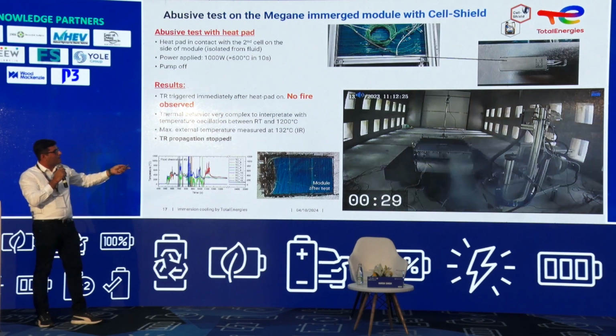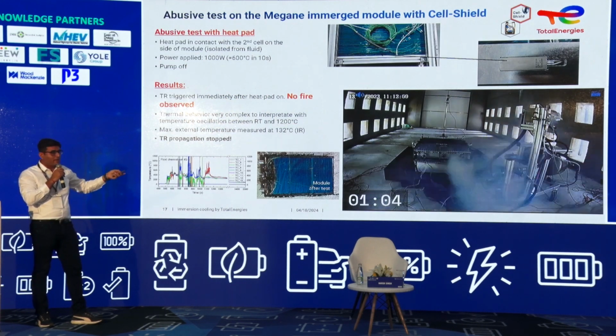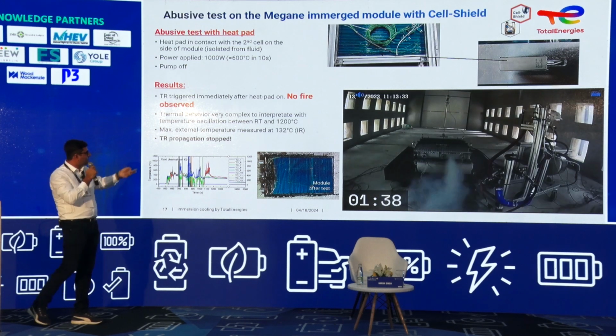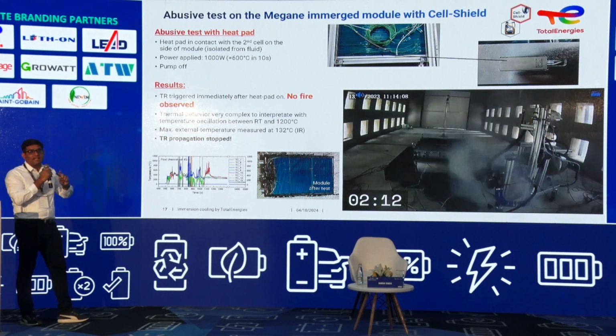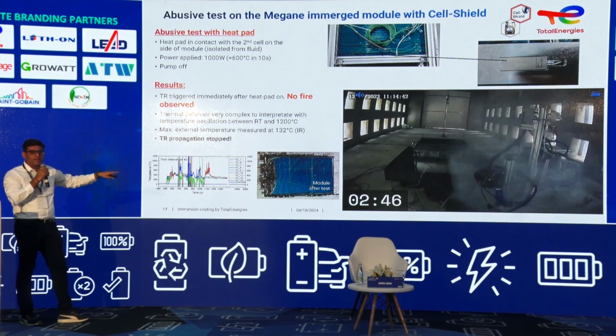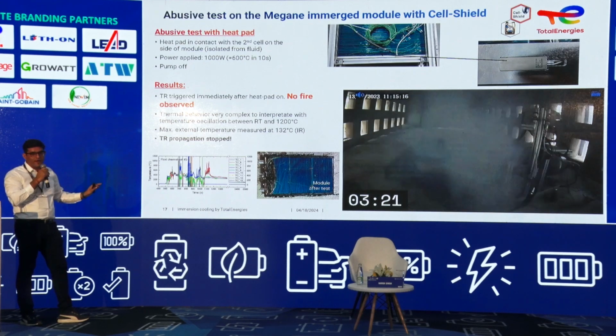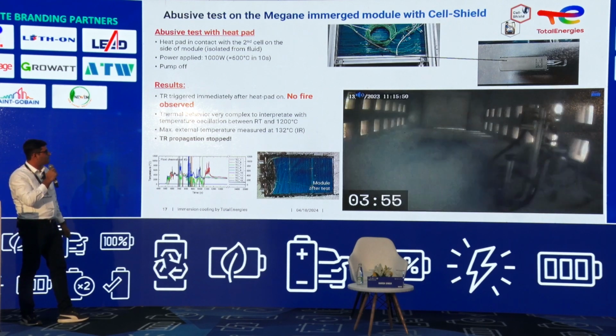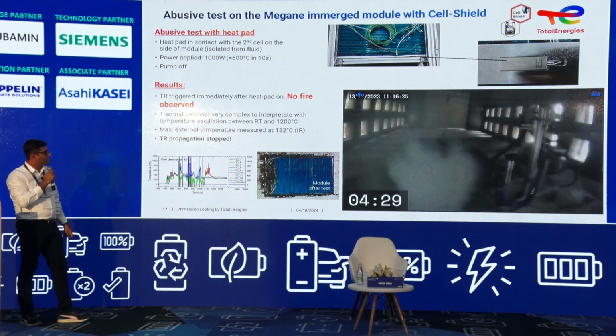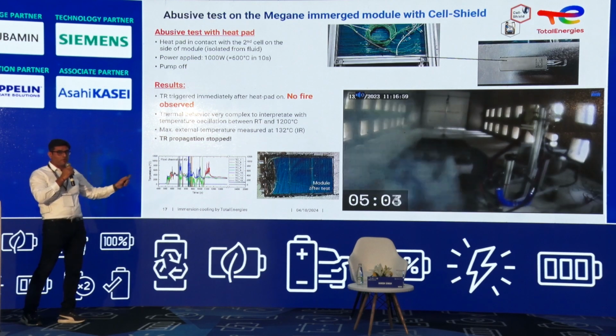We also tested one Megane battery, doing an abusive test, and again we did not witness any fire. This was the immersion cooling battery of the Megane, and again no fire even with thermal propagation. Thermal propagation was there, but it got stopped, and there was no fire.